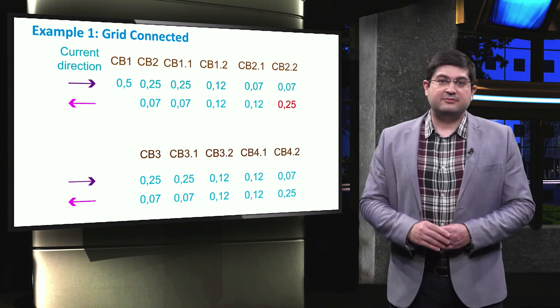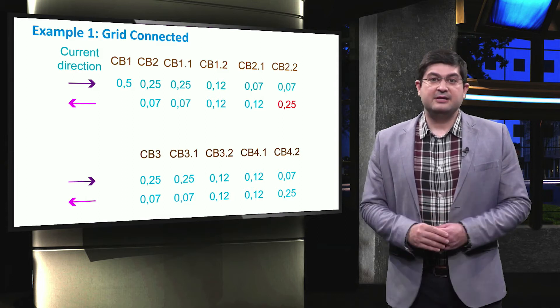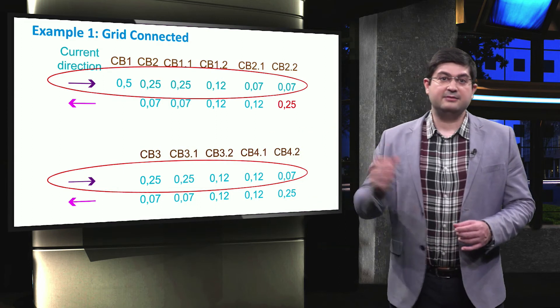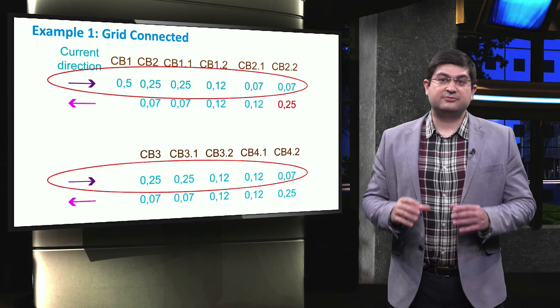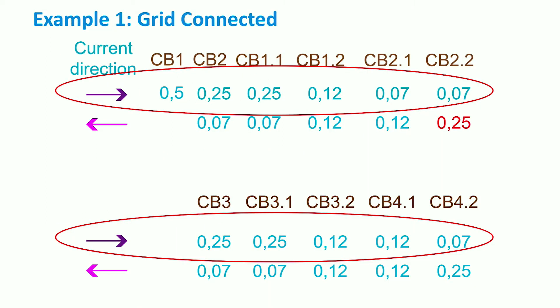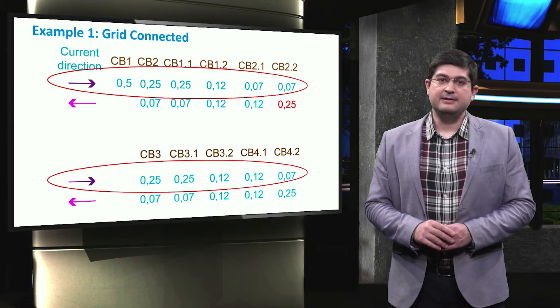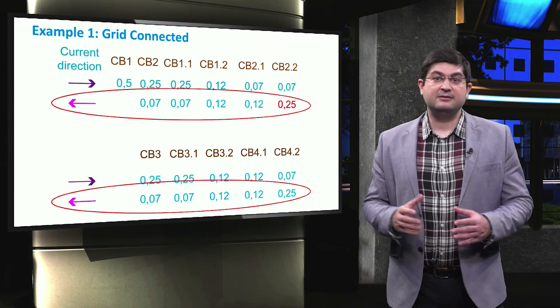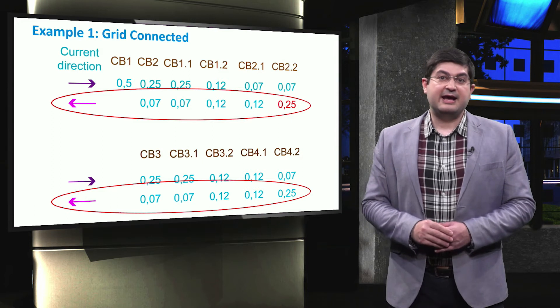In this figure, we show an example of the typical time settings of the directional relays for the first case where switchboards 2 and 4 were disconnected. If the direction of the fault current is from left to right, then the tripping time settings of the relays will reduce from the head of the feeder at circuit breaker 1 to the end of the feeder at circuit breaker 2.2. For instance, if a fault occurs at the end of the feeder, circuit breaker 2.2 will disconnect first after 0.07 seconds. If circuit breaker 2.2 fails to disconnect, then circuit breaker 1.2 will disconnect within 0.12 seconds. On the opposite direction, when the fault current direction is from right to left, the time settings will reduce from the end of the feeder at circuit breaker 2.2 to the head of the feeder at circuit breaker 2.